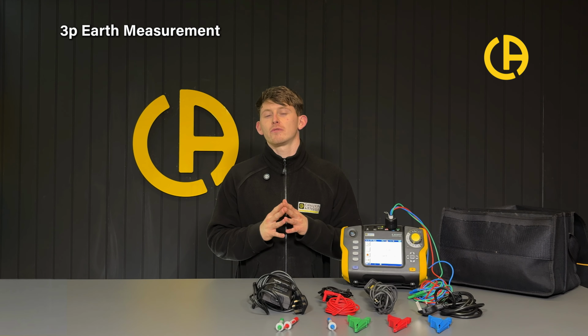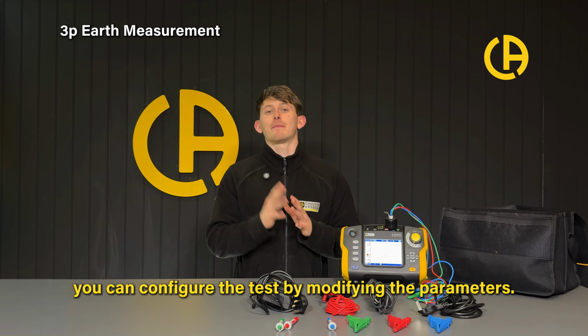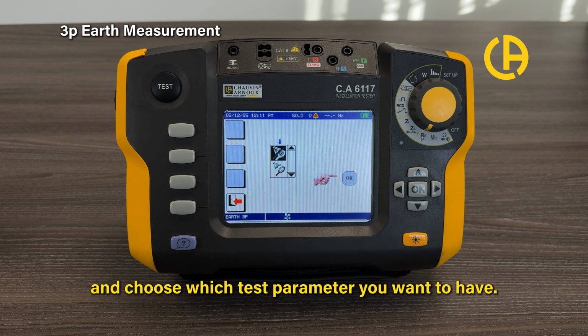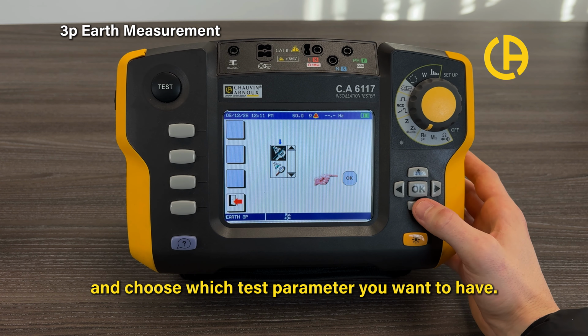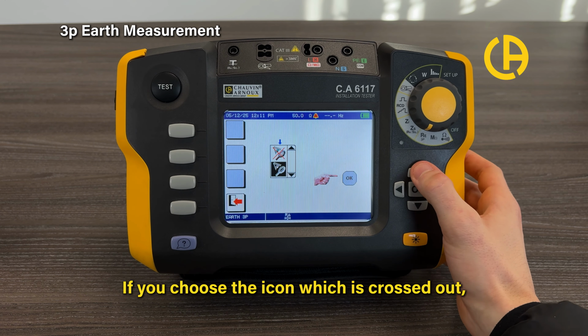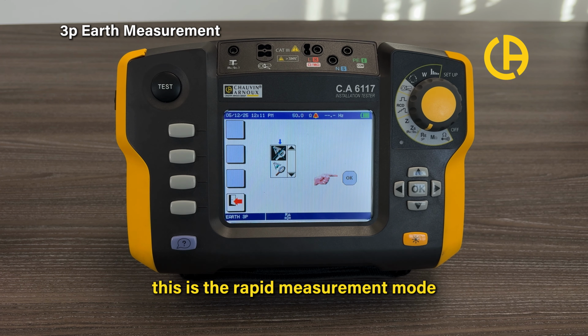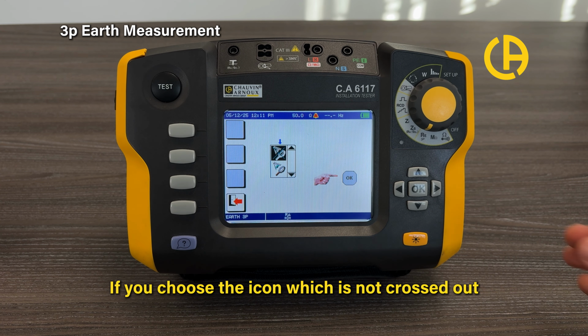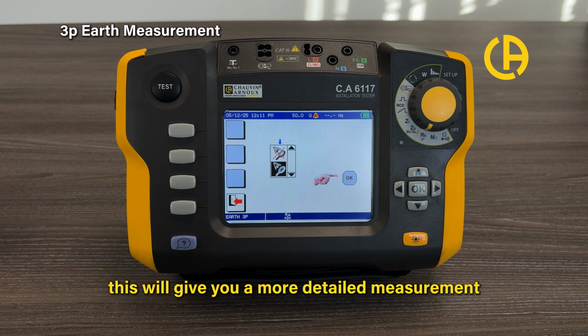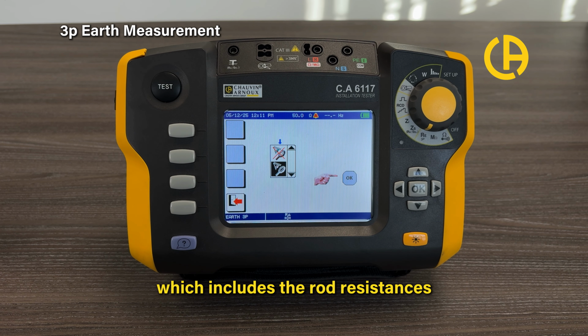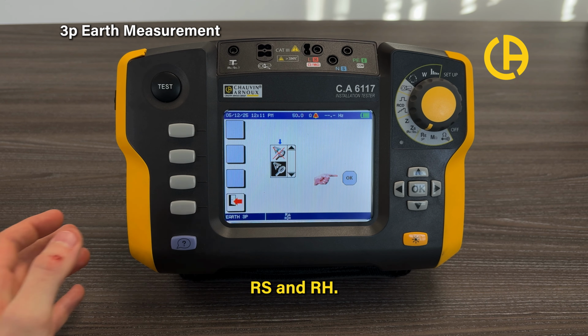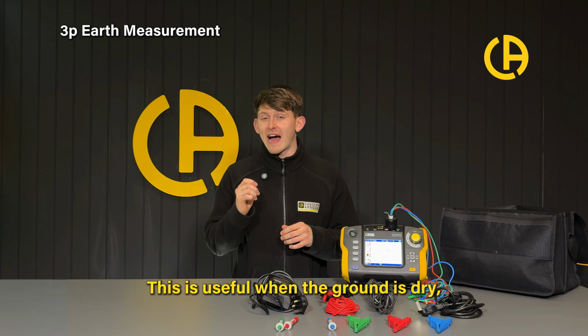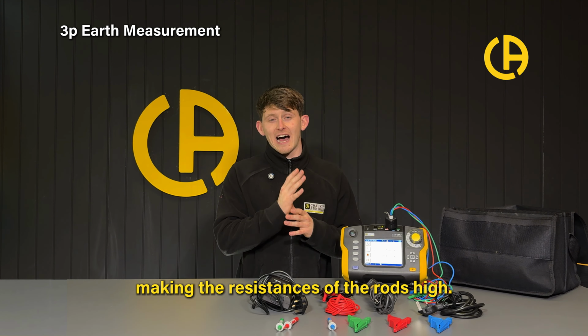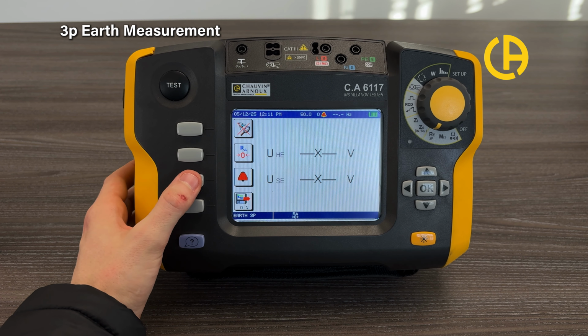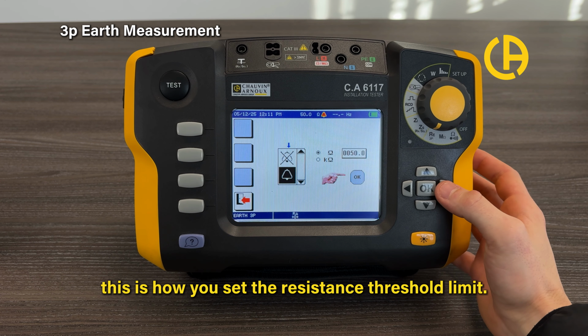Before starting the measurement, you can configure the test by modifying the parameters. Click the magnifying glass and choose which test parameter you want to have. If you choose the icon which is crossed out, this is the rapid measurement mode, which will only measure RE. If you choose the icon which is not crossed out, this will give you a more detailed measurement which includes the rod resistances RS and RH. This is useful when the ground is dry, making the resistances of the rods high. If you press the bell icon, this is how you set the resistance threshold limit.